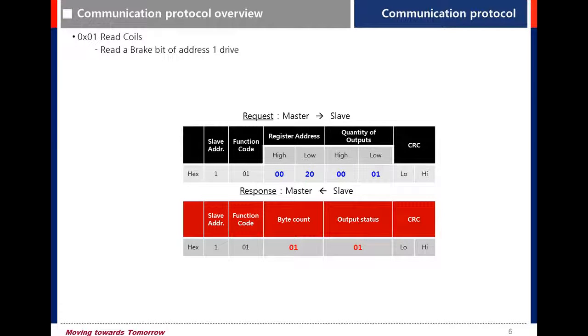Read Coil example: read the brake bit. Slave address is node ID 1, function code 01, register address 20 — the brake address is 20. Quantity of output is 1. Output status 01 means brake is on.